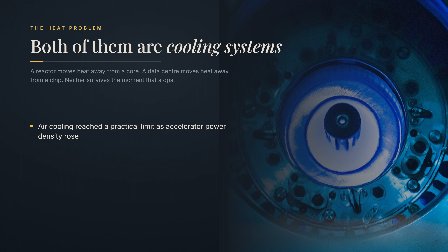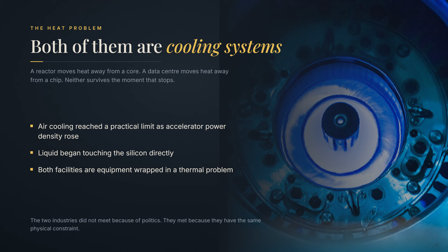Air cooling reached a practical limit as accelerator power density increased, and liquid began touching a cold plate mounted directly above the processor. Coolant flows through a manifold and distribution unit before larger pumps and rooftop coolers reject the heat outside. Almost every additional unit of computing electricity becomes another unit of heat somewhere in the building.